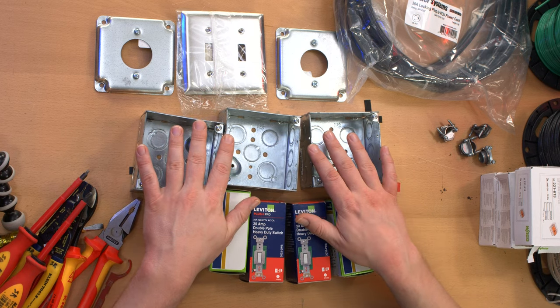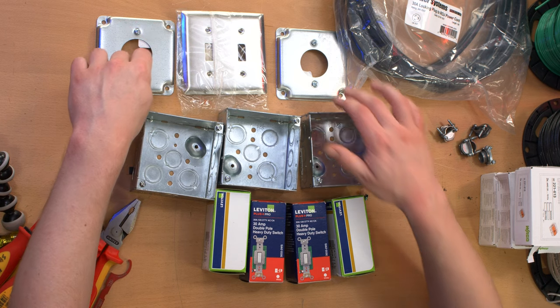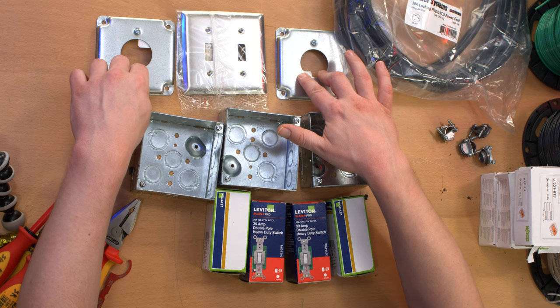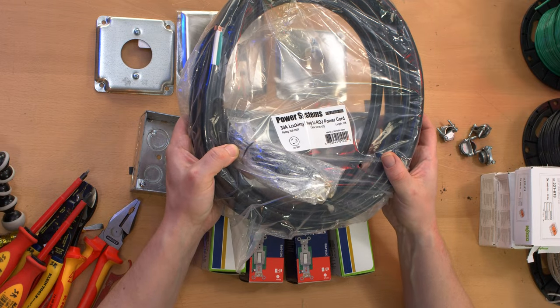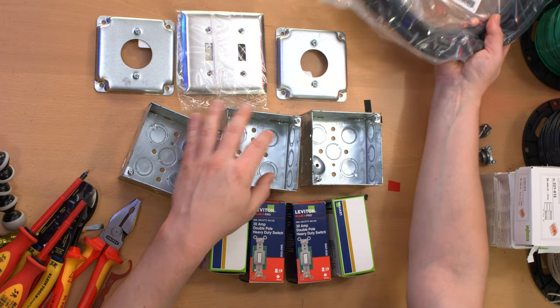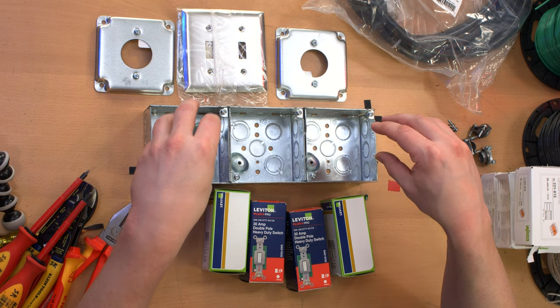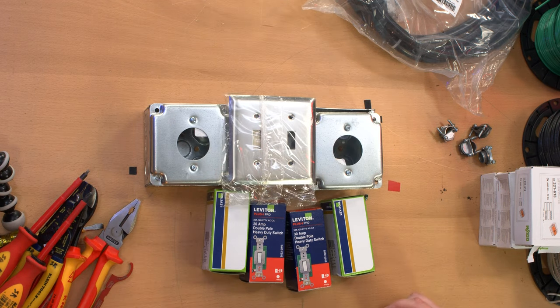So here I've got three 4x4 square boxes — standard work boxes. I've got a double gang switch plate and two plates for the NEMA L6-30R receptacles that are going to go in these. And over here I have a power cord which already has an L6-30P on it, with bare copper on the other end, and it is 15 feet. This will be the power inlet. These boxes are all going to be joined together to form one big box — one mega box — with these two plates like this and then this plate like that.